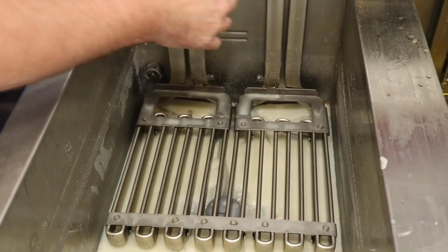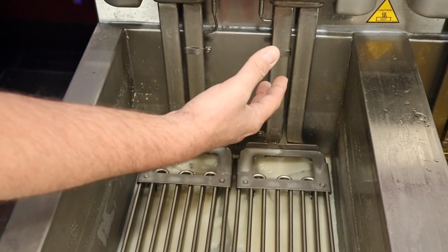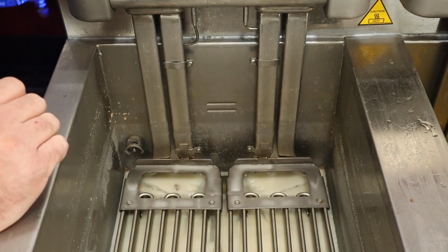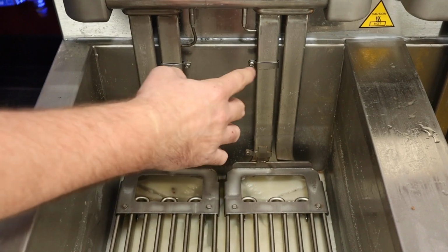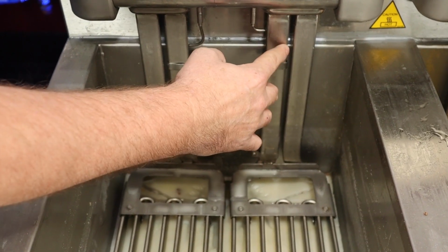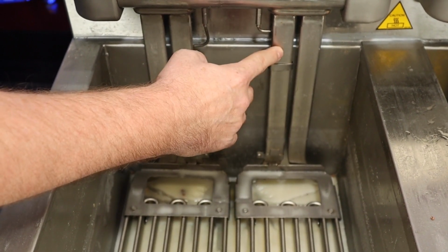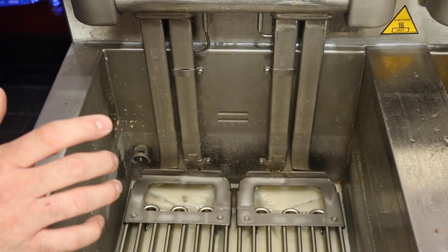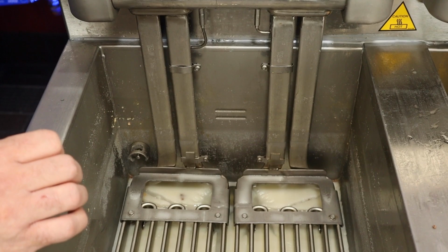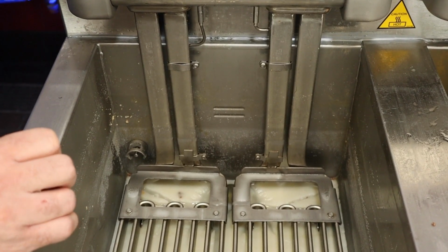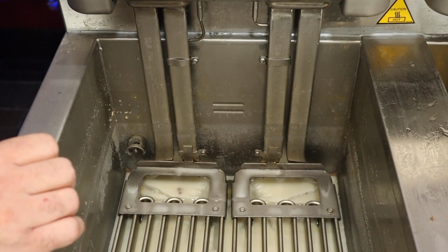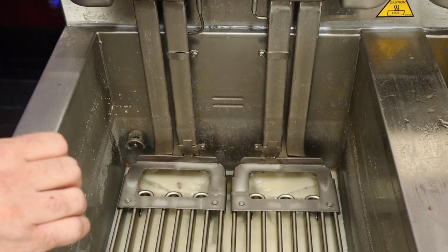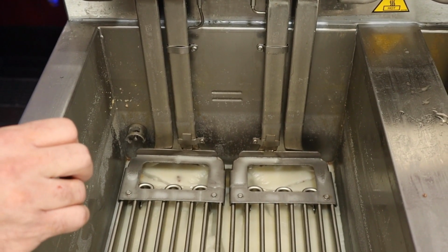And then also something we have to take into consideration that could be causing that error code would actually be maybe one of these elements itself, or on a split VAT, maybe that element only, since we would only have 1 element. Now what I mean by that is we could have one of these legs inside this element that is maybe drawing more amperage than the other. So what we could do is go to the back of the fryer, and then we could take an amp draw on each one of the legs of our element wires to make sure that they are consistent and make sure that we don't have one leg that is pulling more amperage than the other.